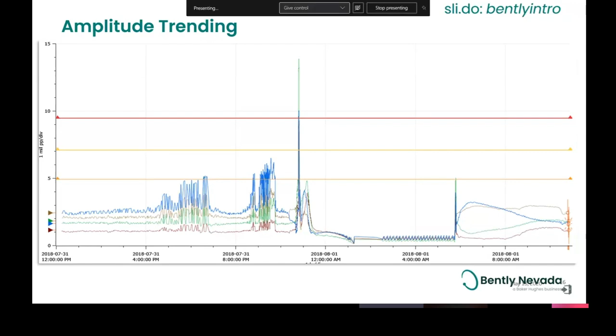But machines do respond differently over time. In this particular example, the customer had been keeping a close eye on his process and noticed that every now and again, the machine would run pretty steady, but then it would start to vibrate a lot. It wouldn't quite reach the alert set point, so the operators didn't see that it was happening, but he noticed that this was going wonky here. So we added another software alarm, a lower alarm. The operators aren't going to see this unless they're looking at the software, for example, System 1, but as a diagnostic engineer, this was very valuable to him to know when this machine was exhibiting this strange behavior, and he could start to correlate it and figure out what the root cause is.